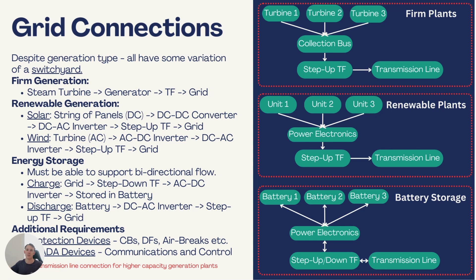So things like 200-300 megawatts. Whereas you can actually get away with a 33 or 66 kV distribution line for some of your smaller solar farms and batteries, for example. So again, it comes down to cost. If you go into the whole effort of installing this big wind farm, you're not going to do it next to a distribution line, which will only allow you to export 10% of your capacity, for example. Being selective with that sort of stuff is always best when you're looking at grid connection.